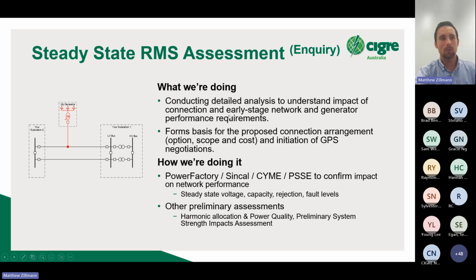As part of this, we're also setting early stage expectations back to the generator to say, based on our studies, this is what we think we're going to need from your generator to support network voltage or to mitigate your impact on network voltage. So you need to be able to support so many VARs of reactive power flow. You'll need to be able to withstand some of these contingency conditions. And so it forms the basis for the proposed connection arrangement.